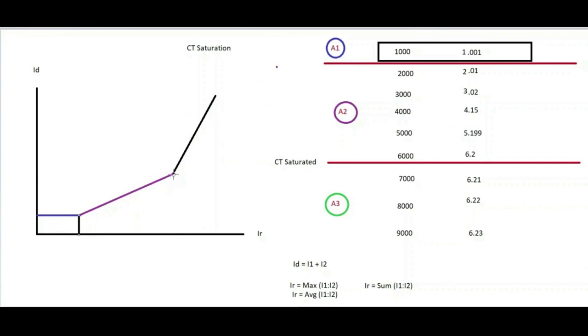Now when I draw this, this area is A1. This area is A2, this area is A3. So, the saturation region. IR means do not trip. ID means trip. So when you plot these two values together, you will identify whether you have to trip or you should not trip. Let's see an example.